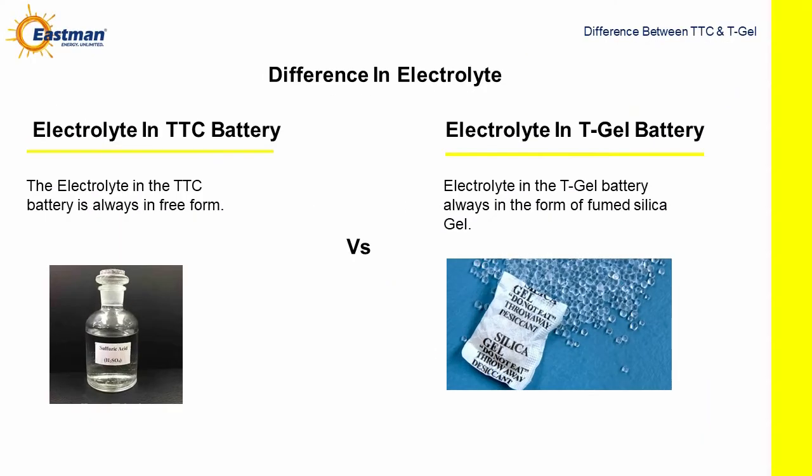Difference in electrolyte. The electrolyte in the TTC battery is always in free form. The electrolyte in the T-Gel battery is always in the form of fumed silica gel.